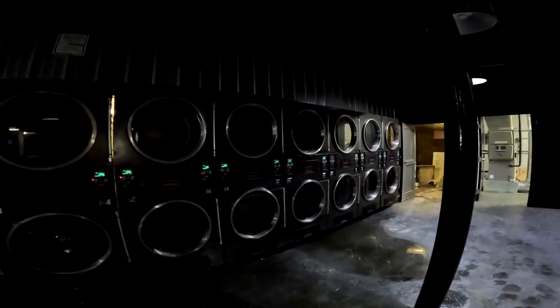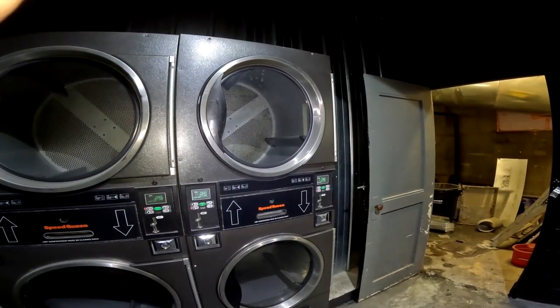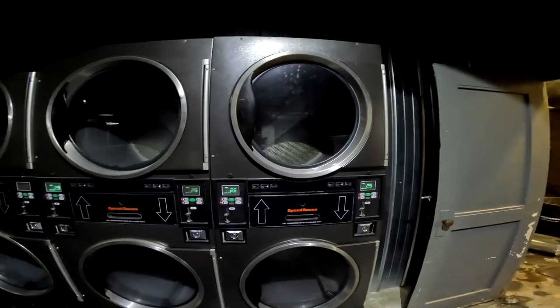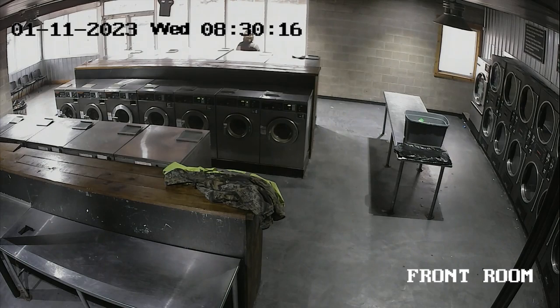It's not really something you want to have happen. I'm going to tell you why this has happened to me. These dryers are big — they're 30-pounders. The normal load should only be about to the center so it can tumble and air can flow through it. What happens is people decide to pack it all the way to the top.